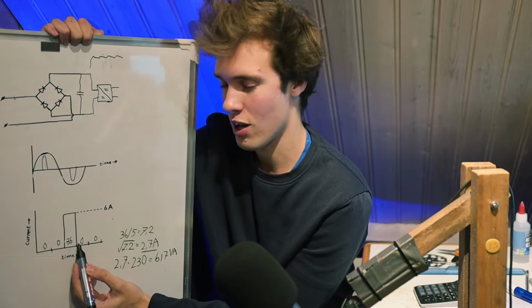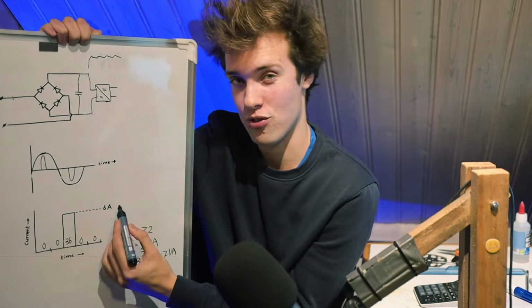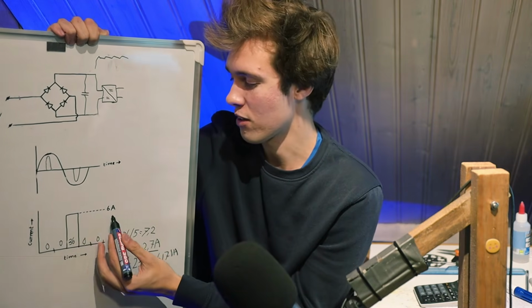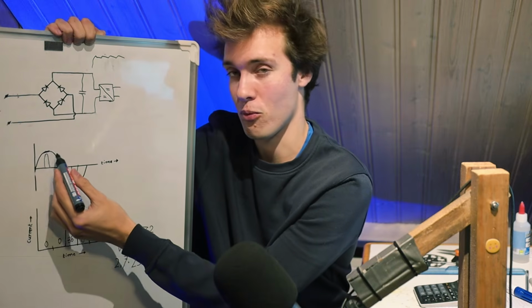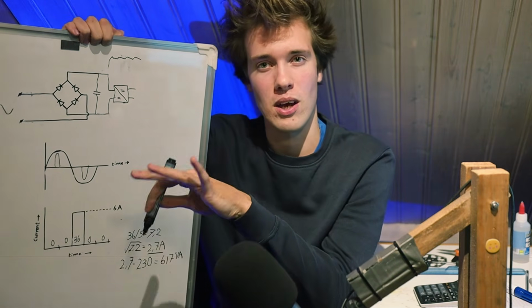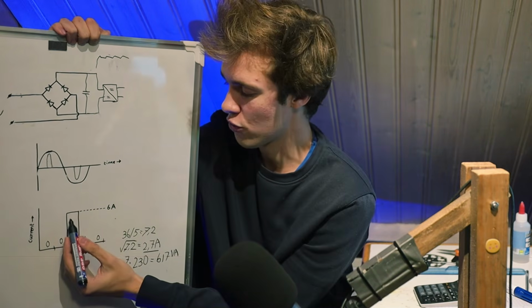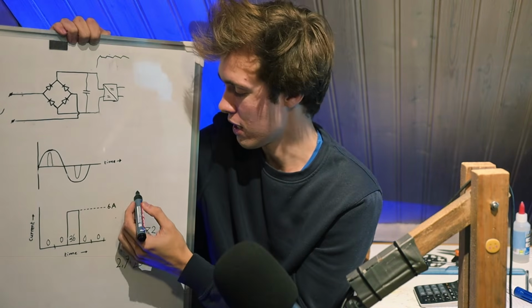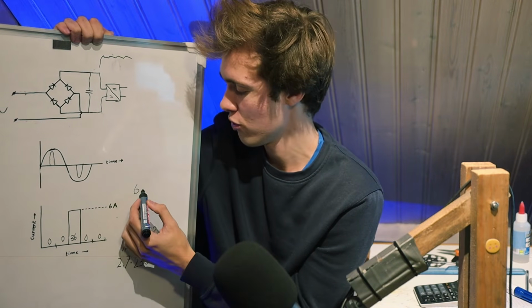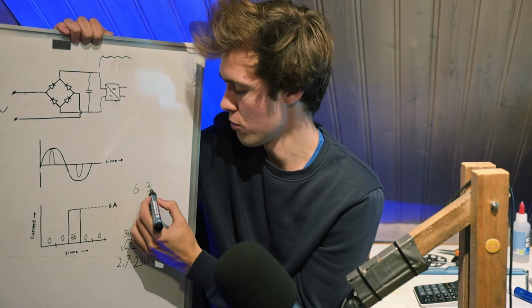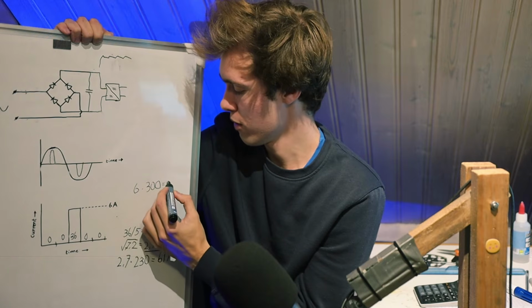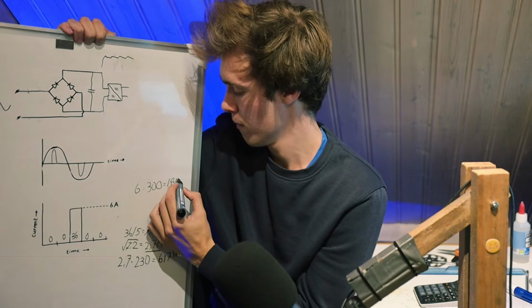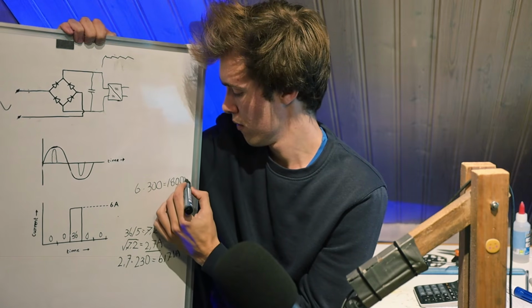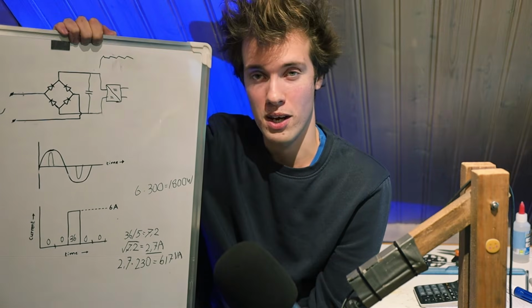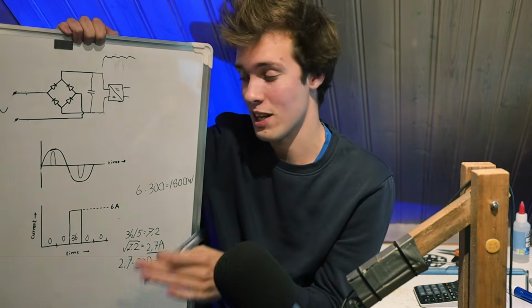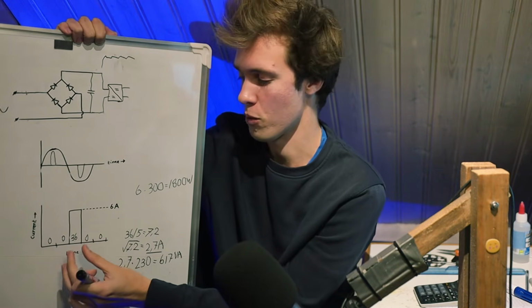During that pulse we are drawing 6 amps of electric current, and it's right near the peak of that sine wave, so I'll say the voltage is around 300 volts. The power during this pulse is approximately 6 amps times 300 volts, which is roughly 1800 watts, a pretty large amount of power, but only during this very short pulse.